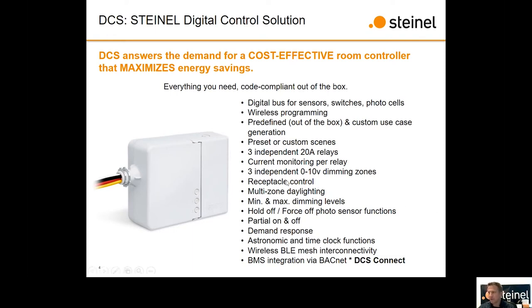So huge advantage for us. And of course, we can monitor current by each relay. So rather than giving you the energy consumption per controller, I can actually monitor the energy consumption for each of those 3 relays. Also, with those 3 independent relays, I've also got 3 0 to 10 volt dimming zones available. As I mentioned, we can do receptacle control because we're 20 amp rated. We've got multi-zone daylighting. We can connect multiple photo sensors onto the same controller. So if you have 2 or 3 or more zones of daylighting that you'd like to control, we can do that all off of one controller.